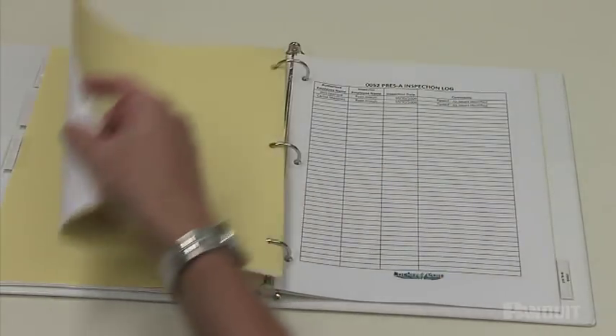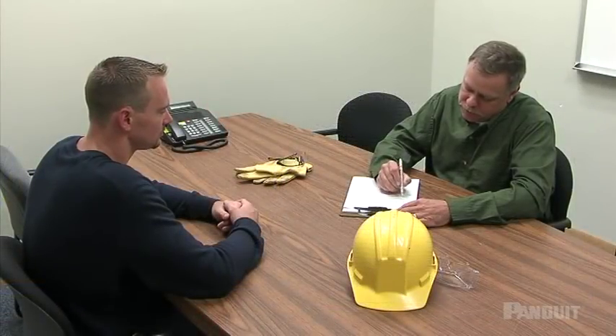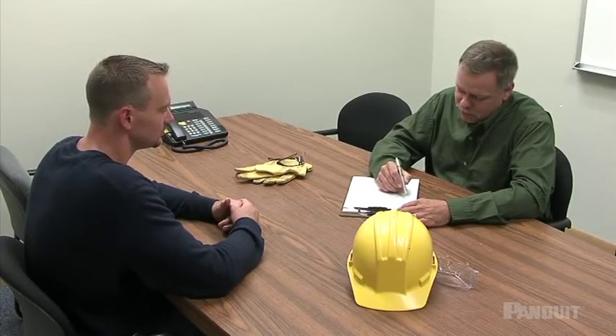Documentation of the periodic inspections must note the machine that is locked and tagged out, the inspection date, the employee responsible for locking and tagging out, and the inspector. When a lockout procedure is inspected, the inspector must review the responsibilities of each authorized employee, ensuring they understand and can properly implement all steps in the procedure. If deviations or inadequacies are found in the employee's knowledge or use of the energy control procedures, retraining should be conducted.